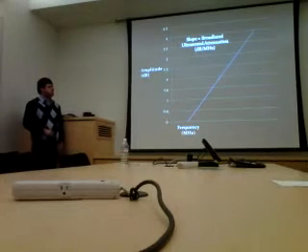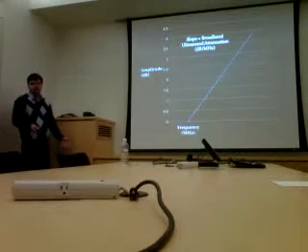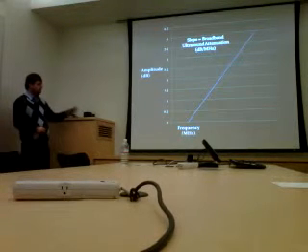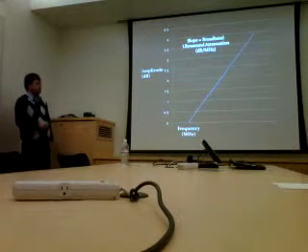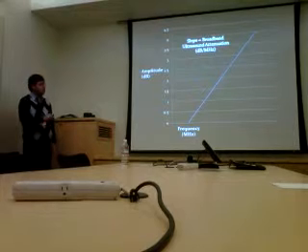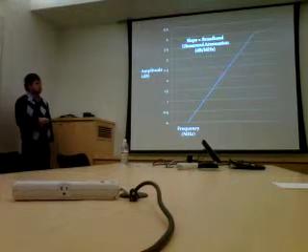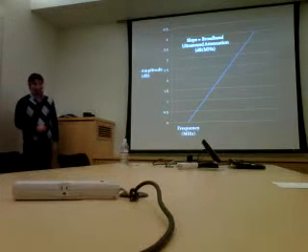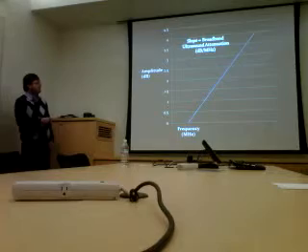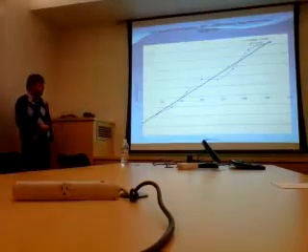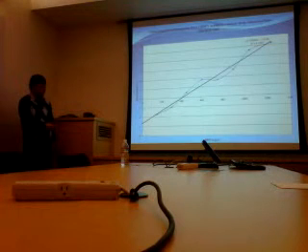Another thing we measure is what we call broadband ultrasound attenuation. The way you get that is you take the amplitude over a range of frequencies, and you get a positive linear slope. The slope is the broadband ultrasound attenuation, which is decibels per megahertz. Now you take that slope of attenuation and plot it versus bone mineral density.